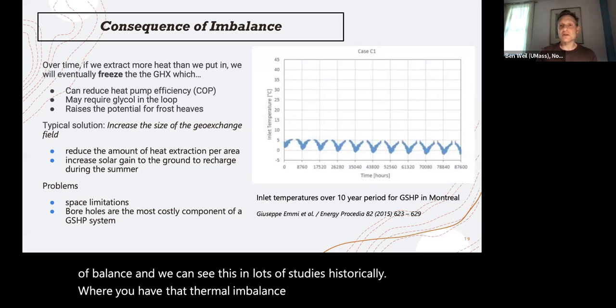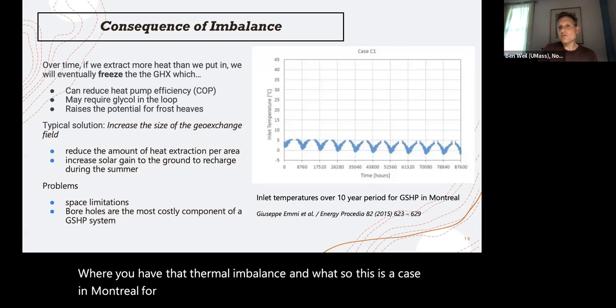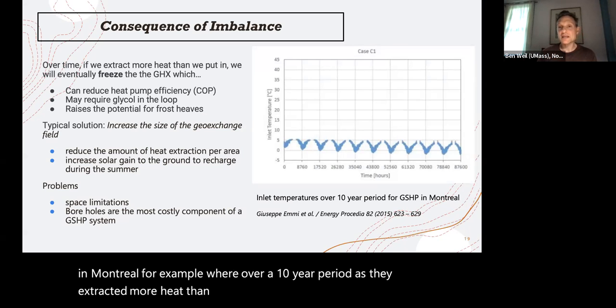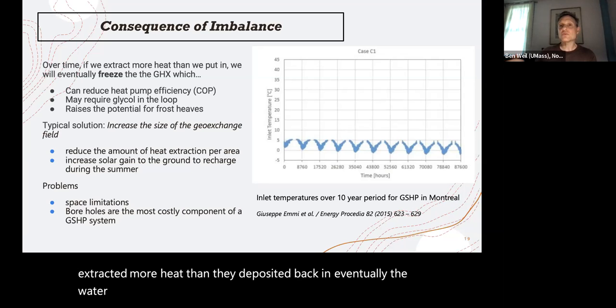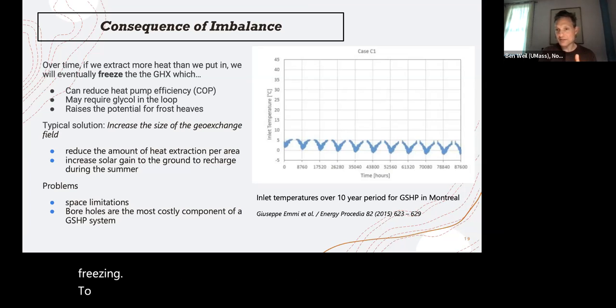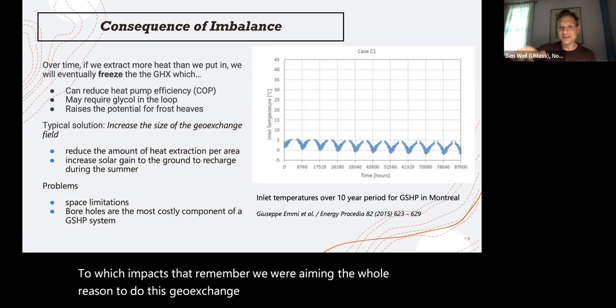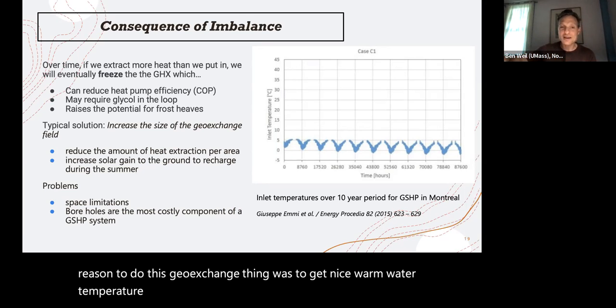So this is a case in Montreal, for example, where over a 10-year period, as they extracted more heat than they deposited back in, eventually the water temperature returning from the ground was lower than freezing, which impacts that. Remember, the whole reason to do this geoexchange thing was to get nice warm water temperature that was constant, but over time we're dropping the temperature so that it isn't any better than an air source heat pump.